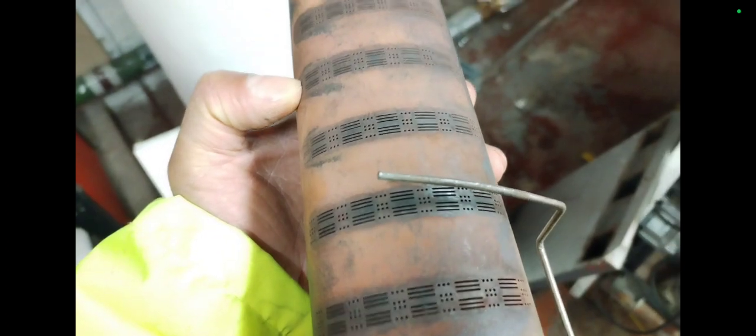Flame detection and ignition changing as well. I gave it a clean down, and here's a look inside to see what is happening, why the unit's not lighting. Because I gave it a wash down and put it all back together, but it was still giving me problems. It was lighting but feels like there was no flame recognition.